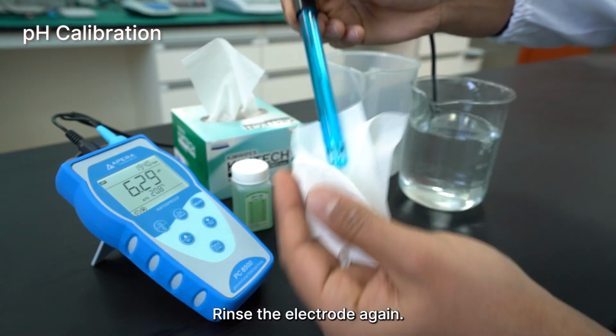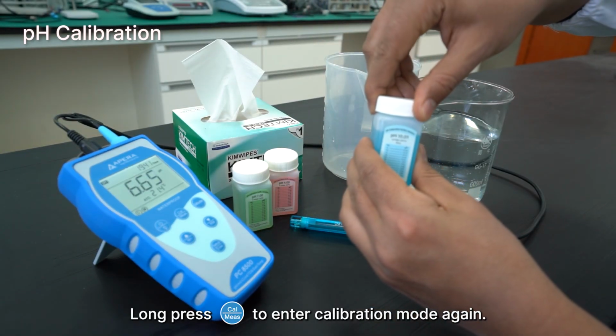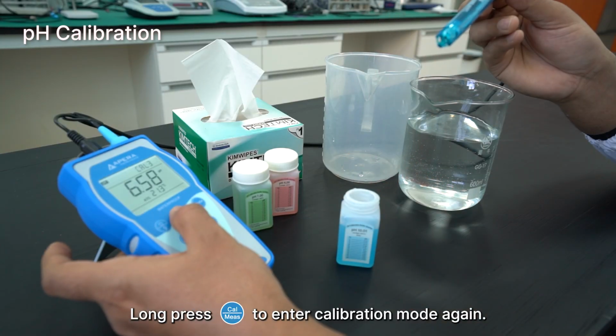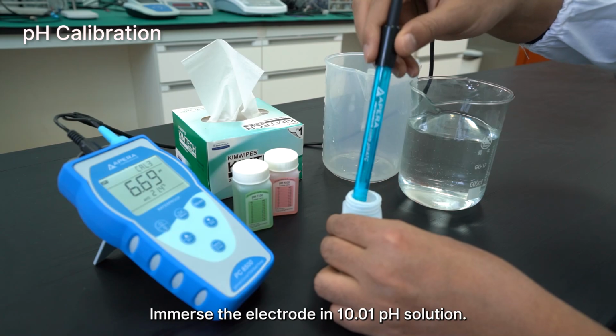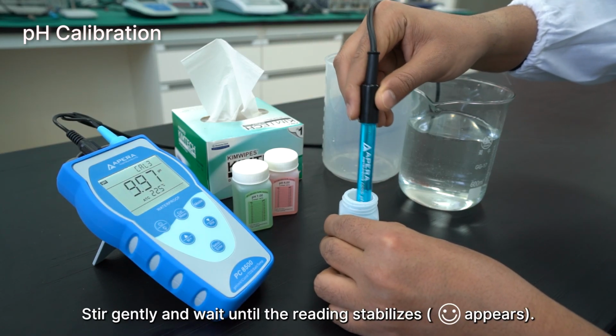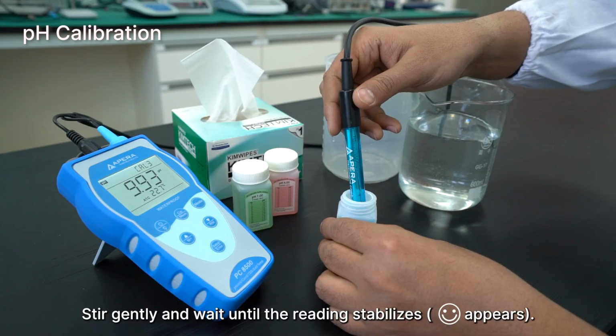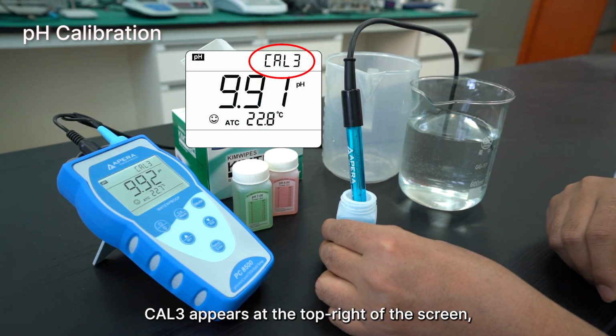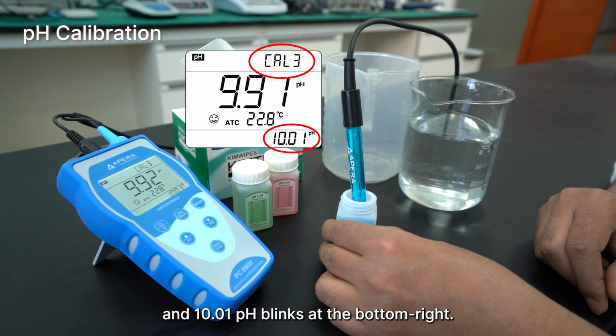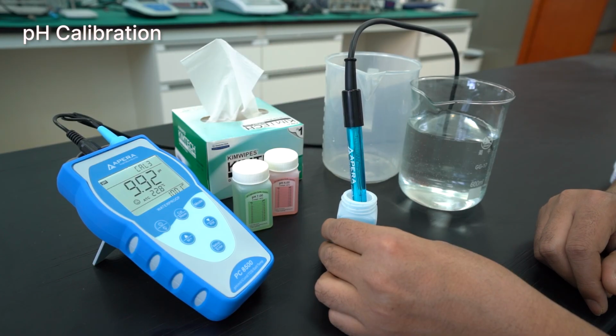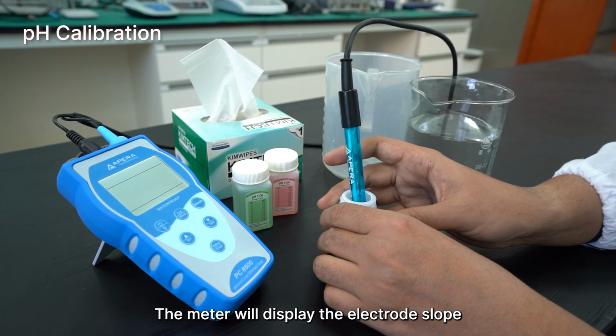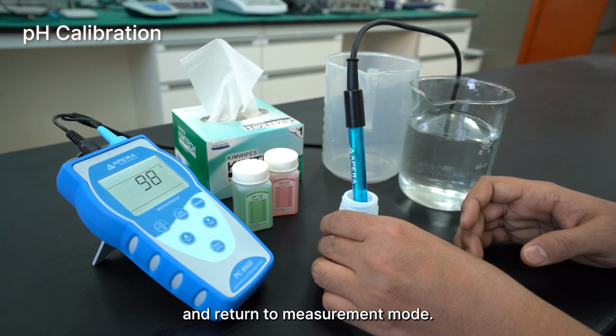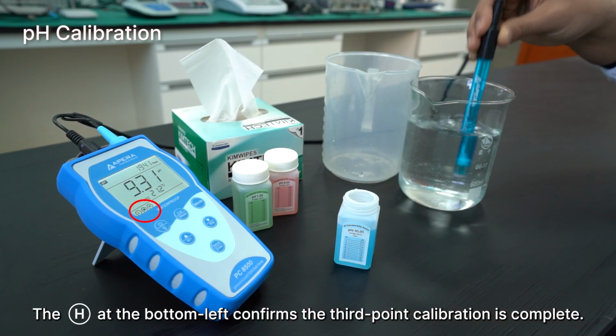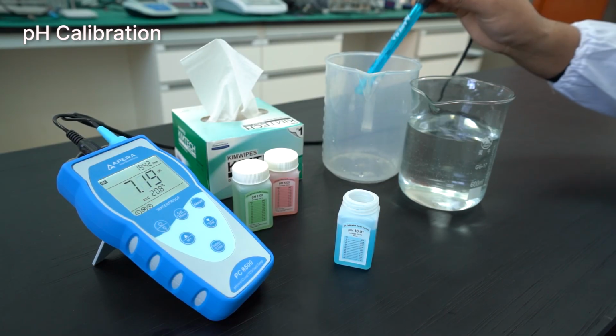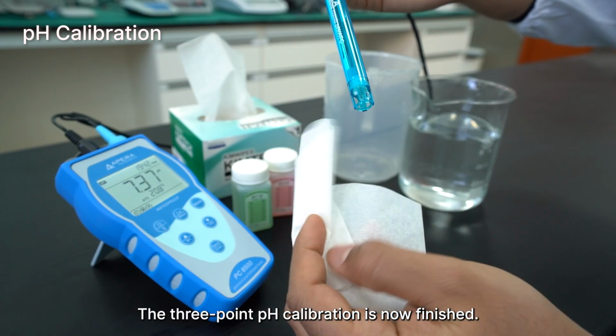Rinse the electrode again. Long press Cal to enter calibration mode again. Immerse the electrode in 10.01 pH solution. Stir gently and wait until the reading stabilizes. Cal 3 appears at the top right of the screen and 10.01 pH blinks at the bottom right. This is the third point calibration. Short press Enter to confirm. The meter will display the electrode slope and return to measurement mode. The H icon at the bottom left confirms the third point calibration is complete. The 3-point pH calibration is now finished.